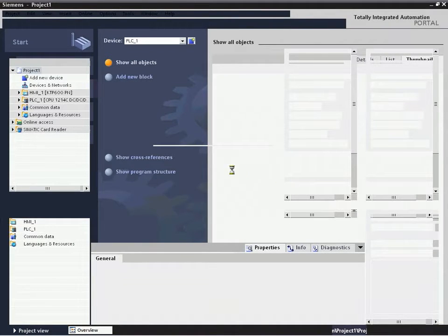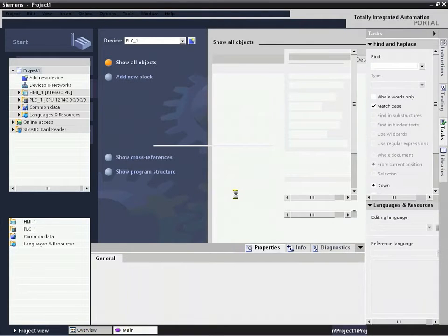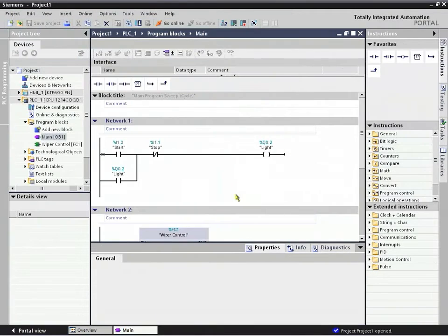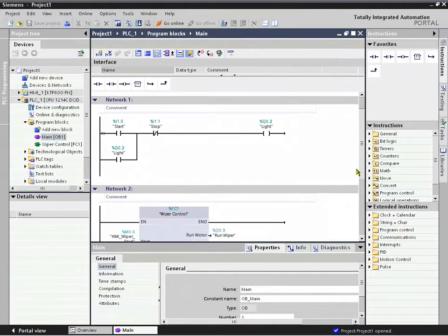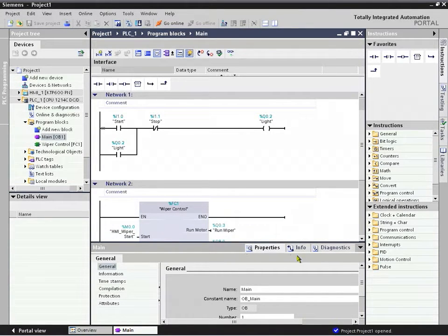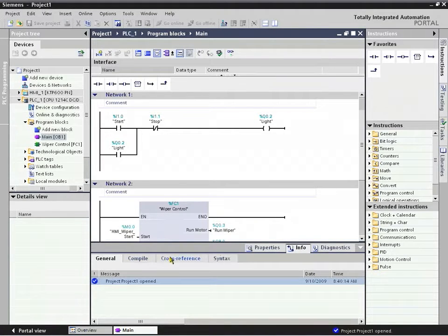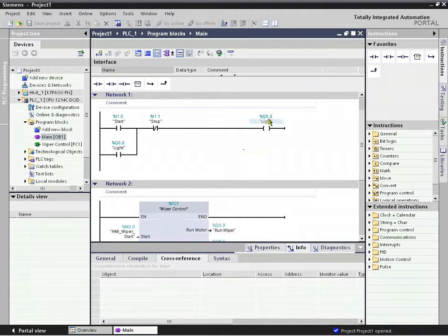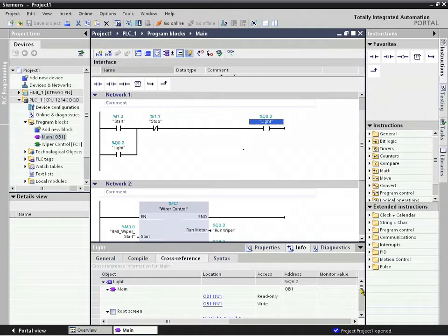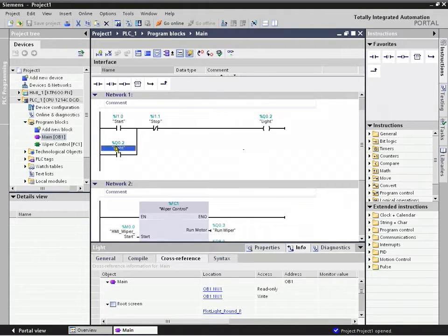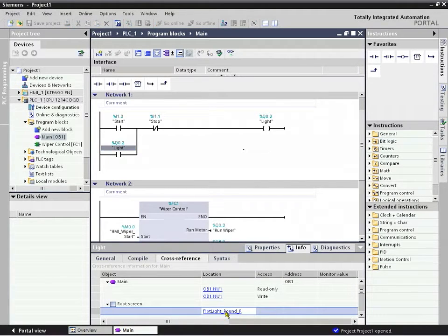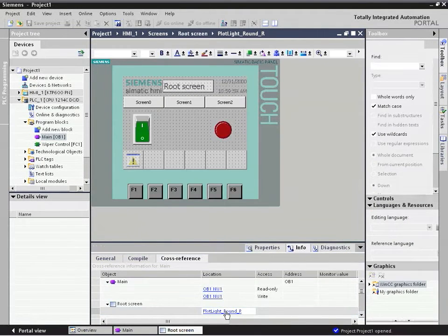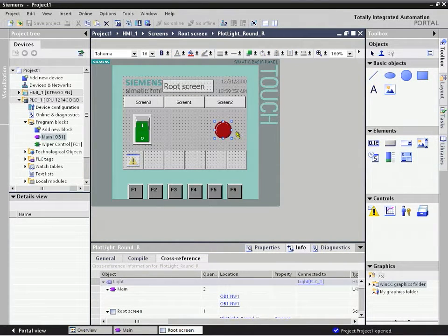From this point, we can look at what we've developed and see where it's being used in other parts of the system-wide project — not only in the logic but in the HMI. From here, our start-stop seal insert that we previously did, we can go to Info and then to Cross-Referencing and click on any one of these elements to see where it's used. You can see we've got it used here, here, and as well it's a pilot light on our root screen of our HMI project. If we click on that, it's all context-sensitive hyperlinked — it goes right to the HMI project, highlights it, and provides the properties accessibility for anything we want to change on that particular element.